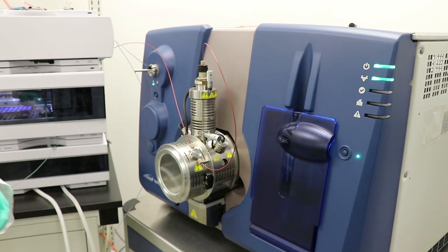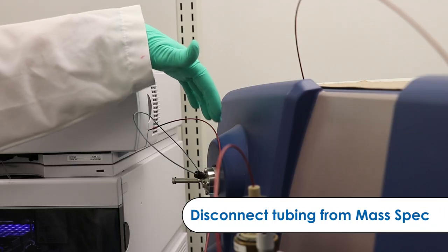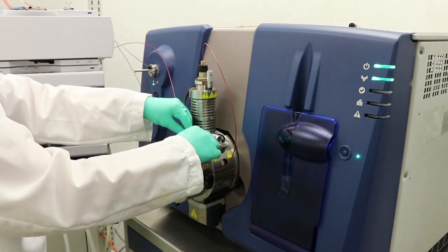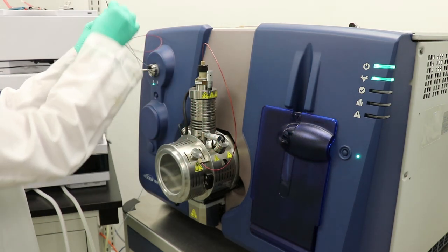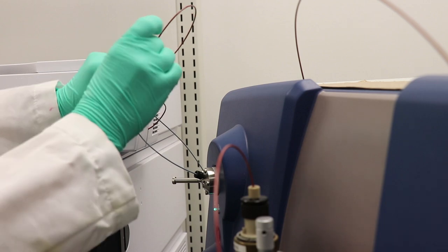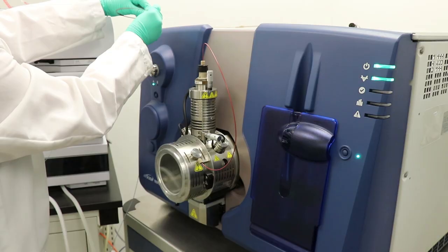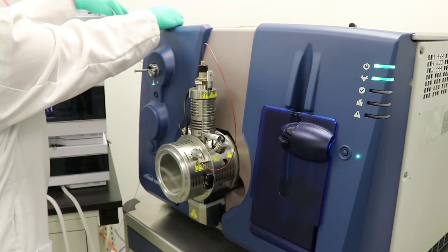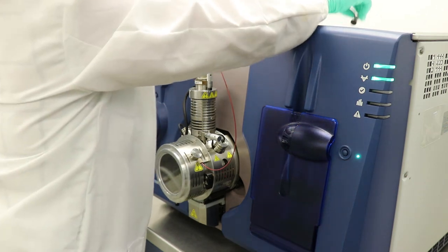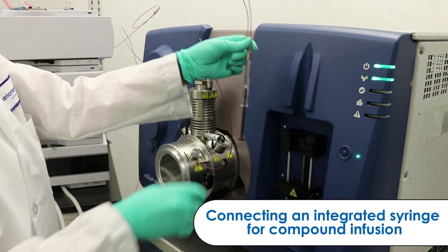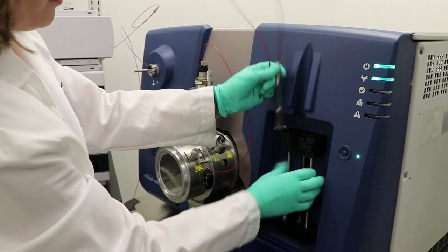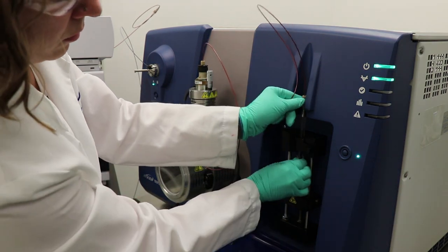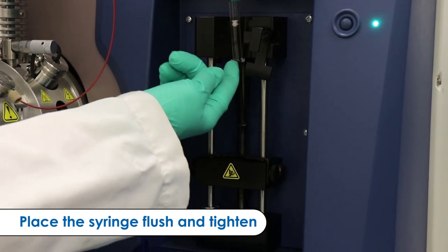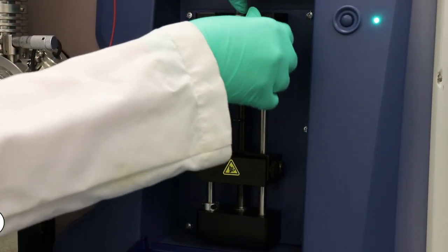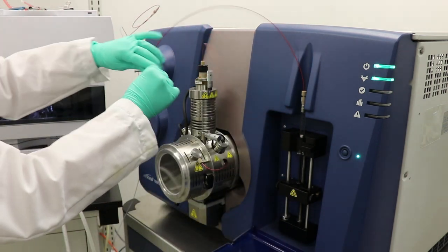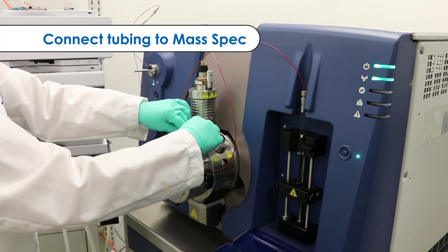Okay, the first thing you're going to do is disconnect your HPLC tubing from your mass spec. This is the tubing that's coming out of the column oven. And I like to wind the tubing around itself so that I don't lose anything. Now on a 4500, you have an integrated syringe pump. So you will take your syringe, you'll open the door to the syringe pump, lower that bar, release the clasp, and place the syringe flush. Tighten it up and make sure nothing wiggles. Now connect the tubing into your mass spec.